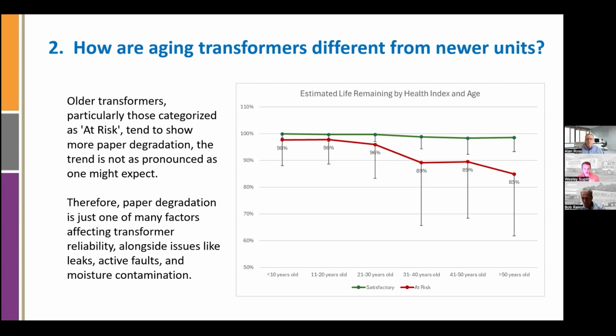Comparatively, newer transformers or comparatively older transformers that have healthy testing results, or newer transformers that have abnormal results, you need to be a little less concerned with the factor of older units and abnormal test results. And this highlights 2 things. First off, that the life of the transformer is the life of the paper, but also there are so many different components of a transformer that you need to monitor and maintain that it is not just the life of the paper you need to be concerned about. That would be like somebody saying, it's just your heart health you need to be concerned about. Well, there's a lot of other health factors and characteristics that you need to monitor and maintain.